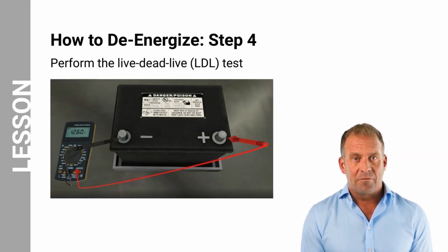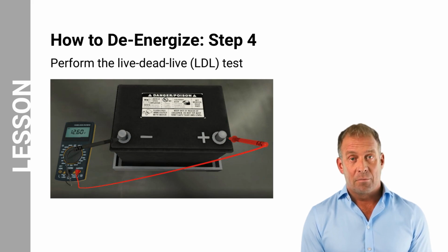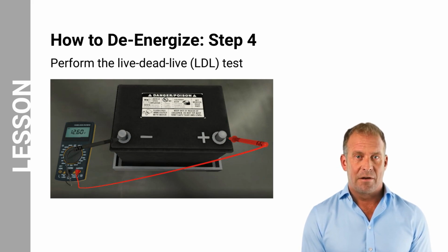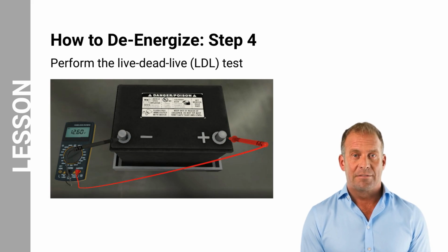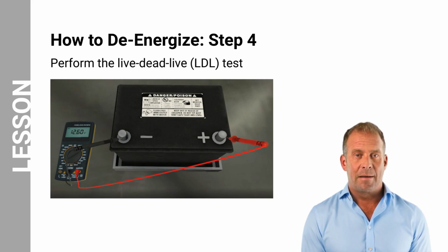Step 4. Before initiating the power-down procedure, ensure that all meters and adapters are functional and undamaged. Perform the live-dead-live test to verify their functionality. This test is crucial to confirm that the tools are operational during testing and have not been damaged during the process. Before beginning the live-dead-live test, gather all meters and adapters that will be used during the testing process.